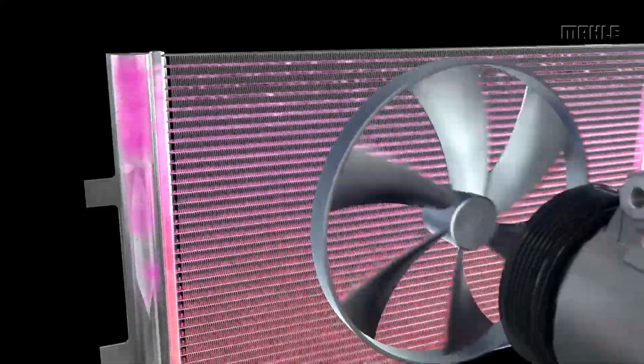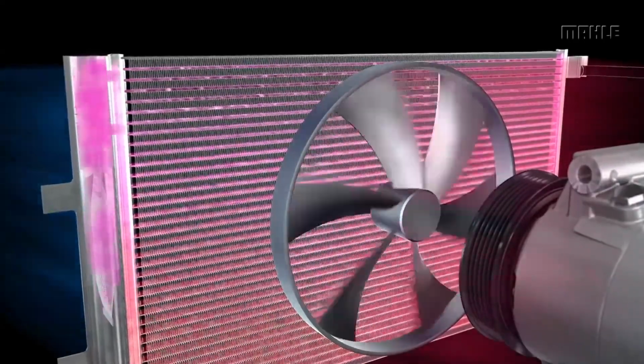That said, multi-speed or variable heat pumps are more efficient because at low output, the heat exchangers are vastly oversized, meaning we are transferring a small amount of energy over a very large heat exchanger surface. As output increases, the ratio decreases, and it becomes harder to squeeze a larger amount of thermal energy across that same heat exchanger surface, requiring larger delta T, so the heat pump has to work harder to generate higher temperatures.